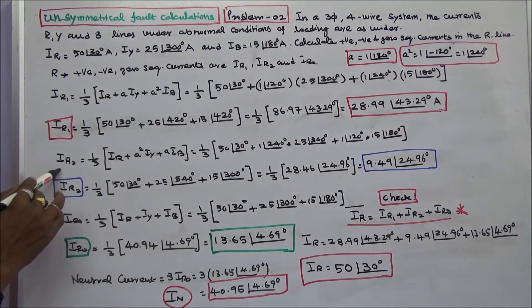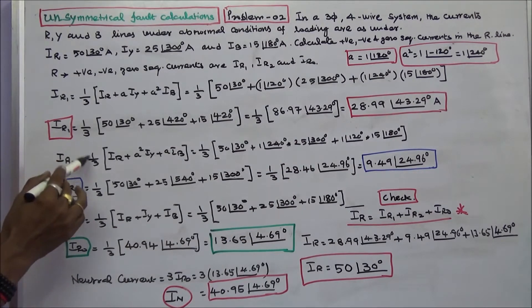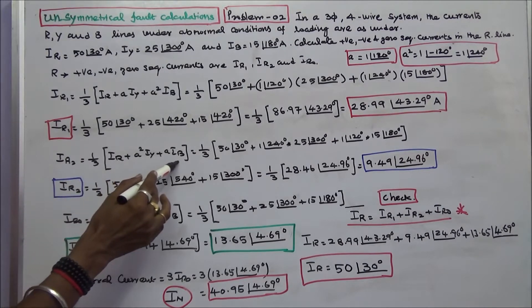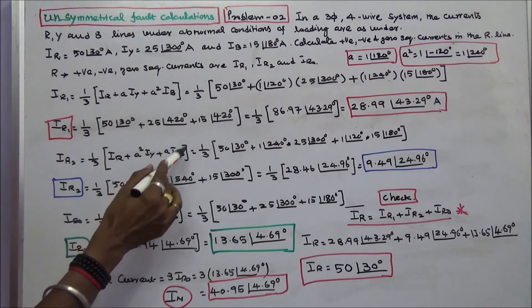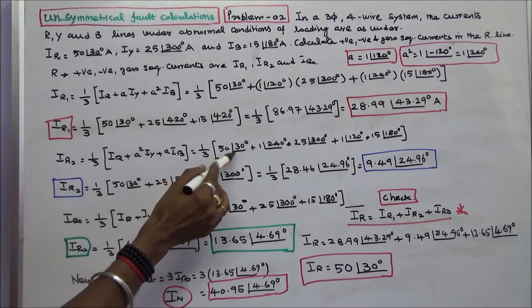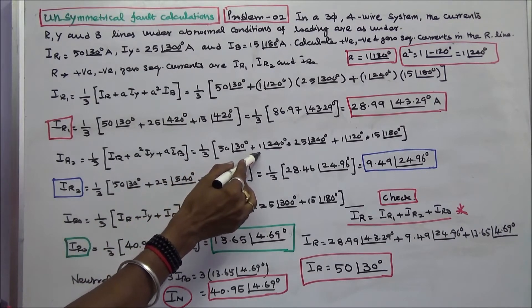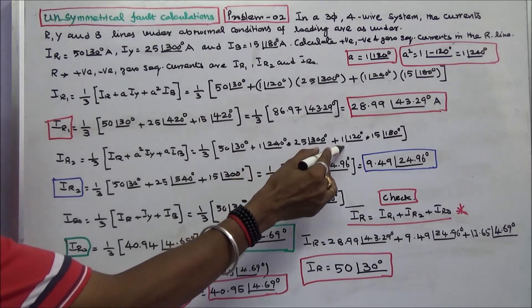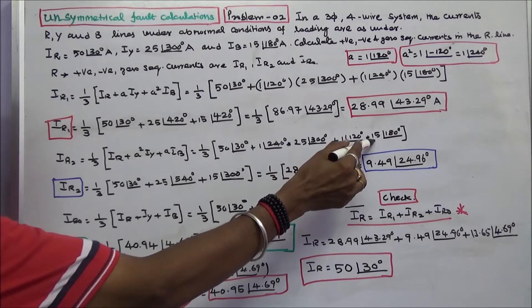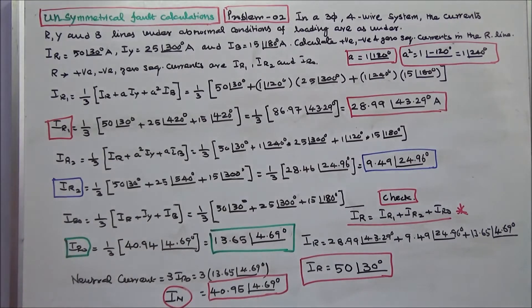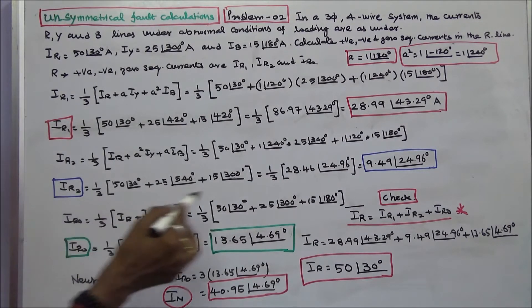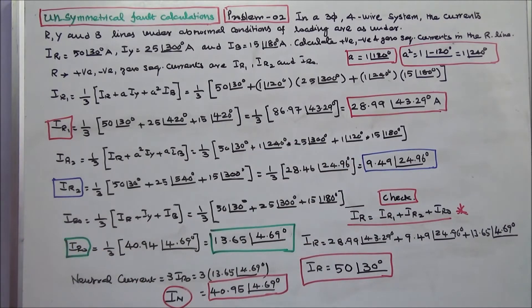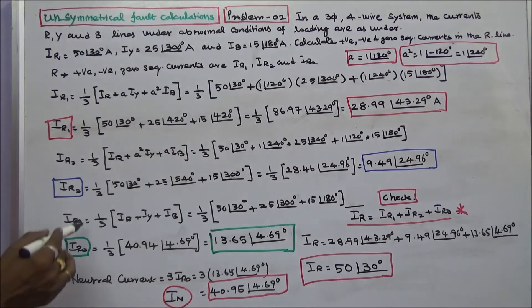Next, IR2, the negative sequence current: 1/3 into (IR + A²·IY + A·IB). That is equal to 1/3 into [50 angle 30 + (1 angle 240)(25 angle 300) + (1 angle 120)(15 angle 180 degrees)]. Negative sequence current IR2 is equal to 9.49 angle 24.96 degrees.